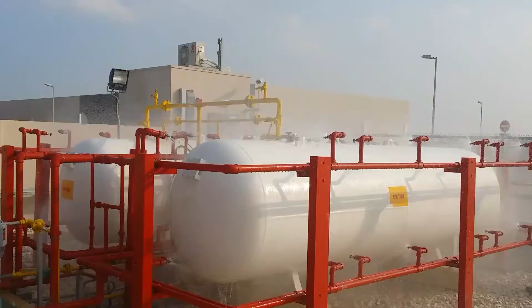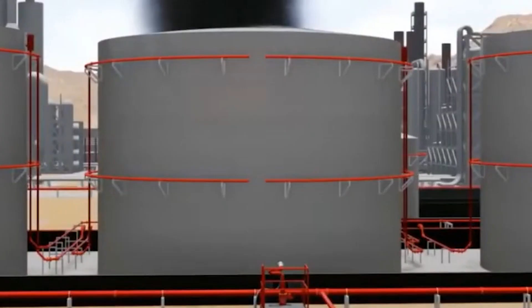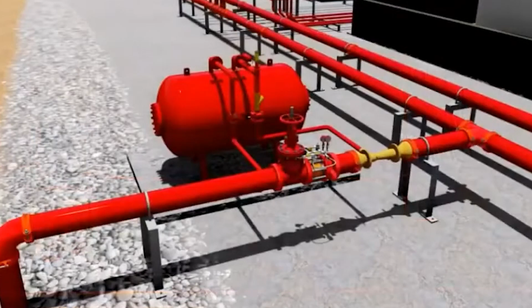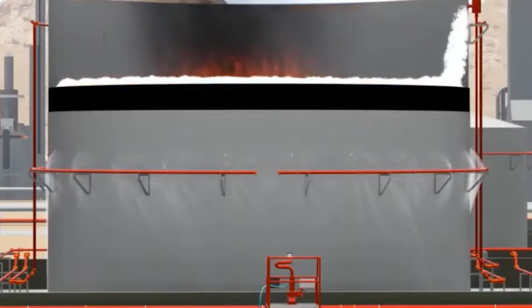As per the UAE Fire and Life Safety Code, when a building is not sprinklered and LPG tanks are installed above ground or on elevated platforms like roofs or podiums, it is mandatory to install a dry type deluge spray system. This system acts as a first line of defense, providing rapid cooling and fire suppression in case of a fire involving LPG tanks. The deluge spray system is designed with a breaching inlet, allowing firefighters to connect hoses and supply water to the system efficiently during emergencies.